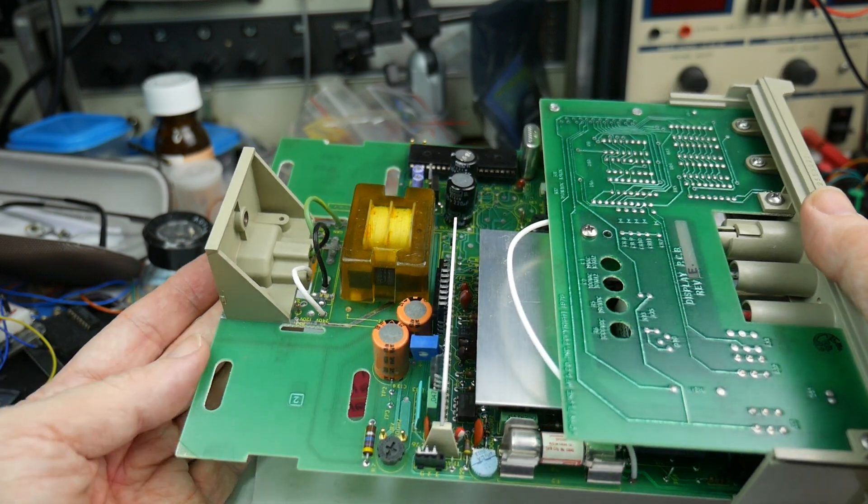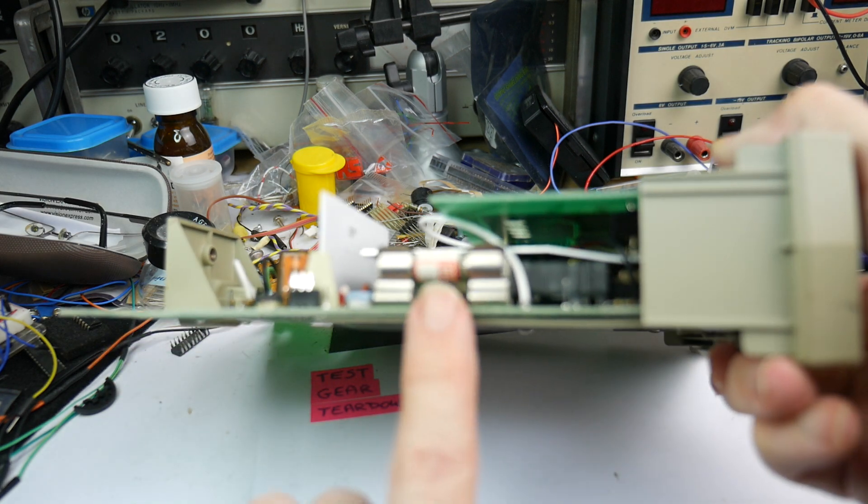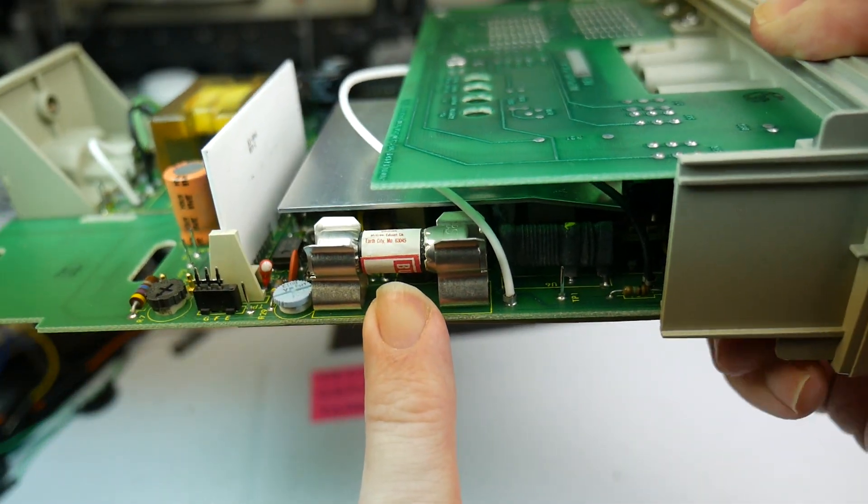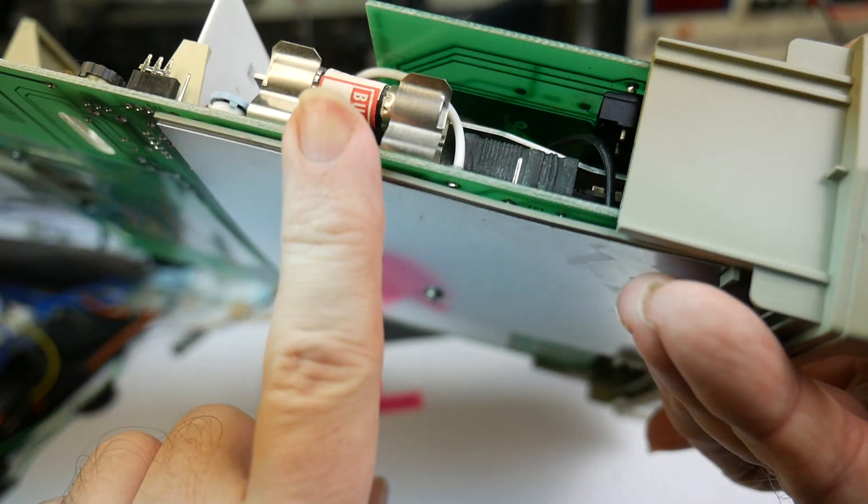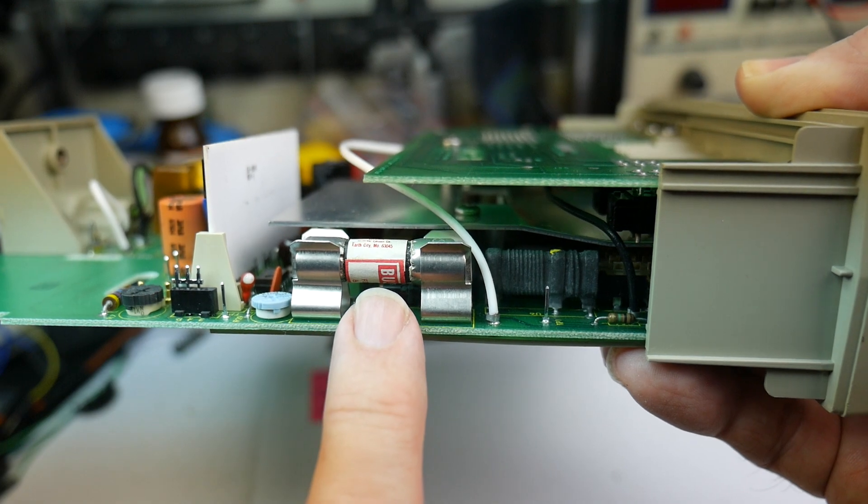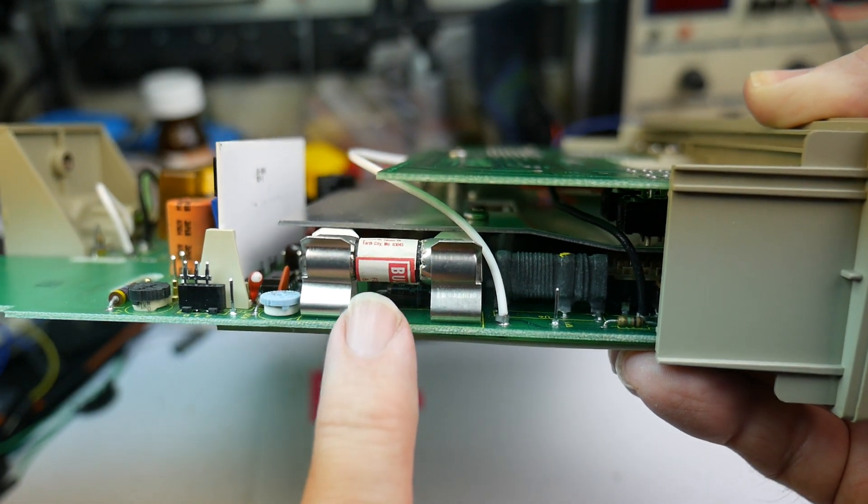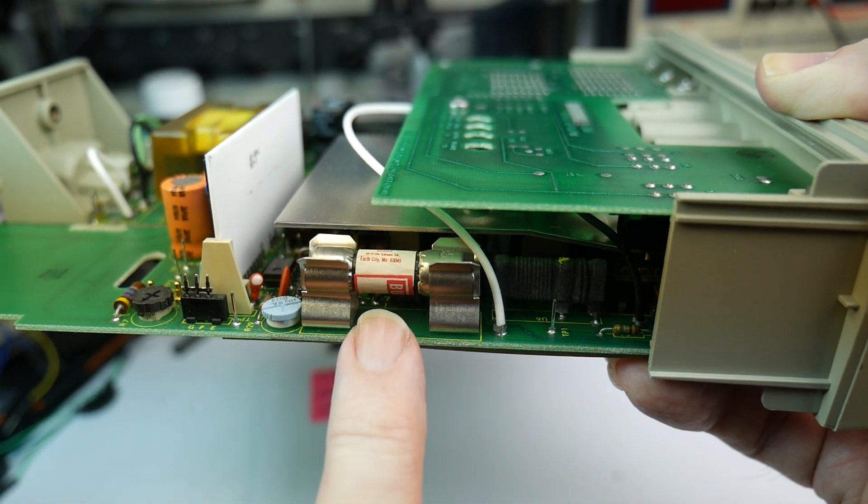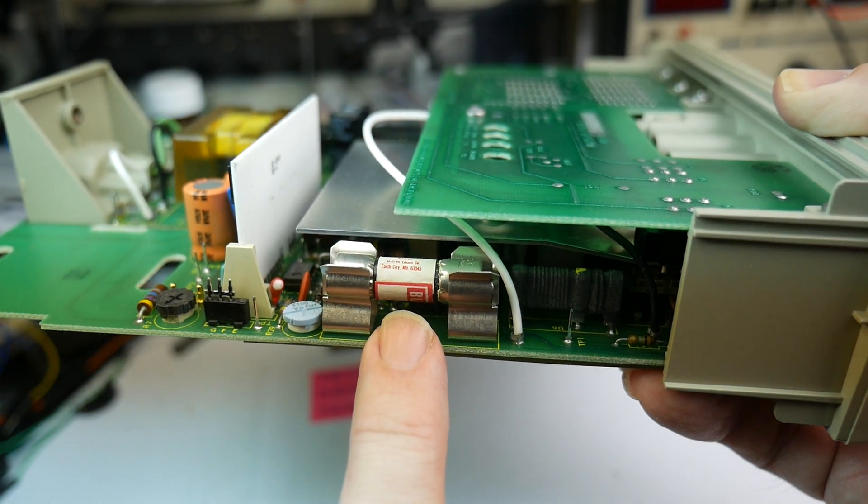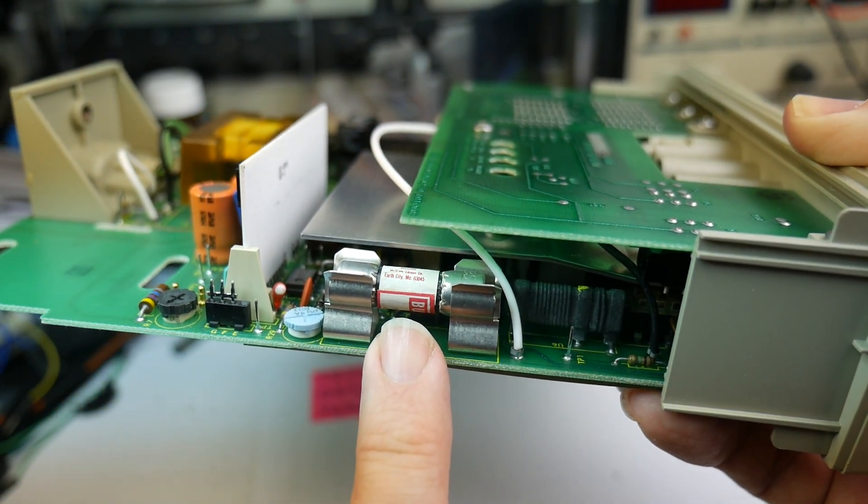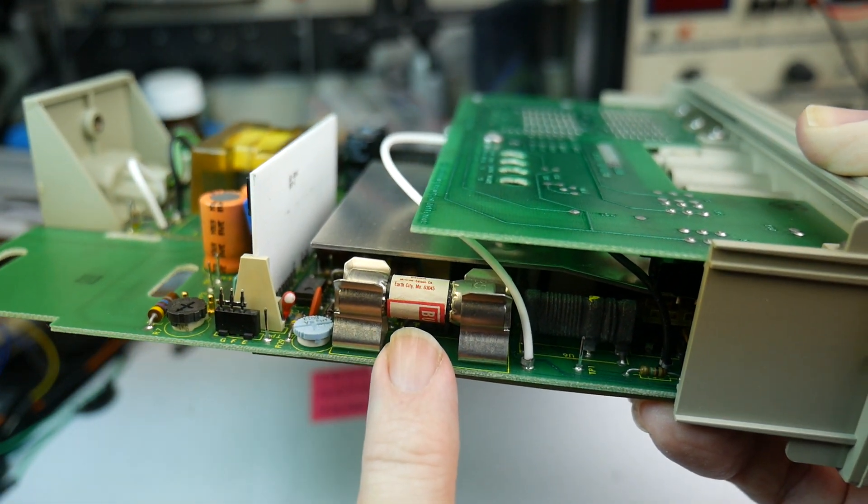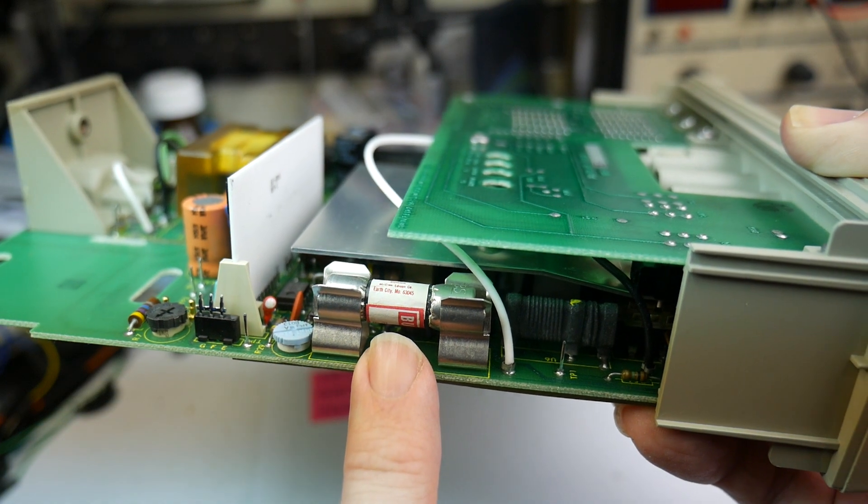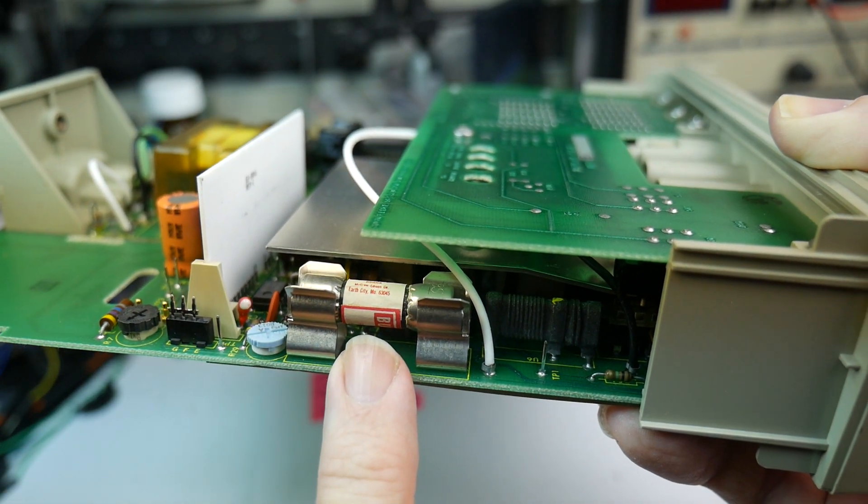Nothing unusual in here. Now here is an internal fuse. This is actually a much bigger fuse, physically and electrically. I think it's a 10 amp rated fuse. That is the fantastic safety feature of nearly all Flukes. It's a much bigger physically thing, and the reason for that is this is capable of blowing in extreme fault conditions. The fuse in the little socket on the front, the 2 amp one, there is a slim chance—it is a risk—that that fuse could, rather than blow, simply arc in certain extreme cases with lots of energy behind the circuit.